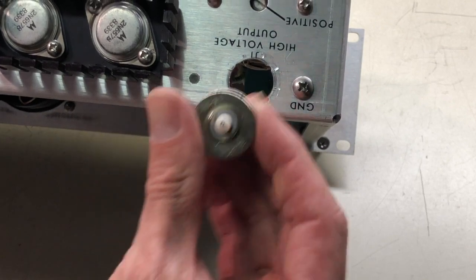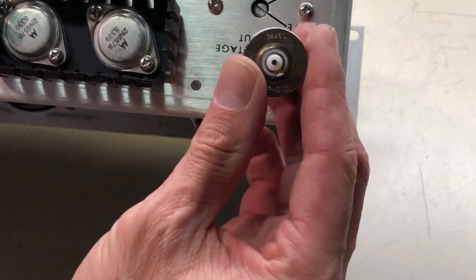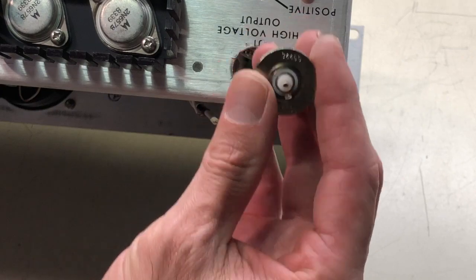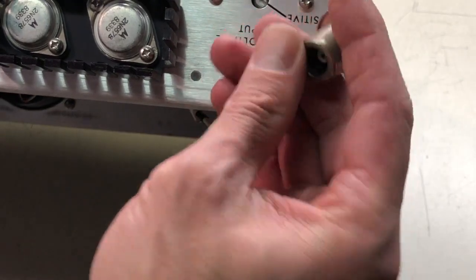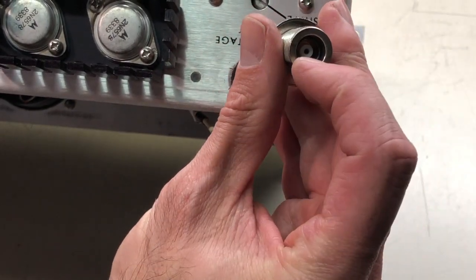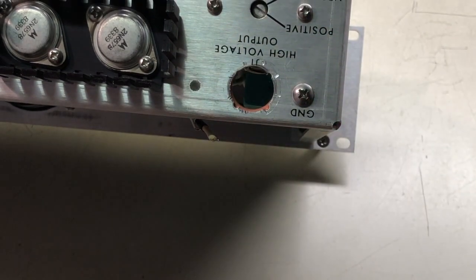So I'm not going to put the heat shrink tubing on the back of this connector, but I will install it because it'll give us a point to probe into that center socket, and we can take some readings and verify that the output can go. We still haven't turned up to 1,000 volts yet, so I want to make sure that the output can at least go up to the full output.